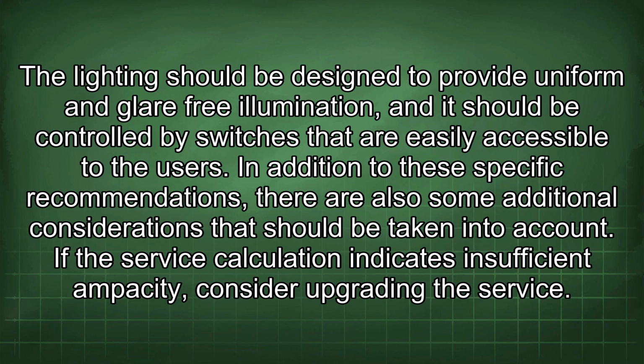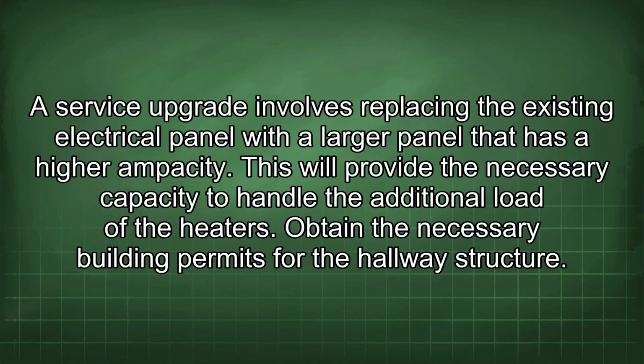In addition to these specific recommendations, there are also some additional considerations that should be taken into account. If the service calculation indicates insufficient ampacity, consider upgrading the service. A service upgrade involves replacing the existing electrical panel with a larger panel that has a higher ampacity. This will provide the necessary capacity to handle the additional load of the heaters.